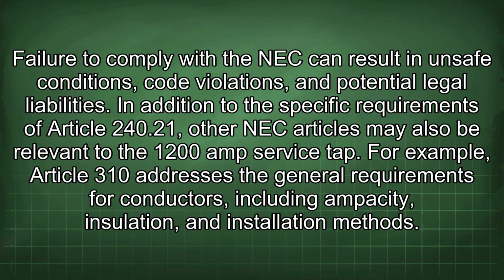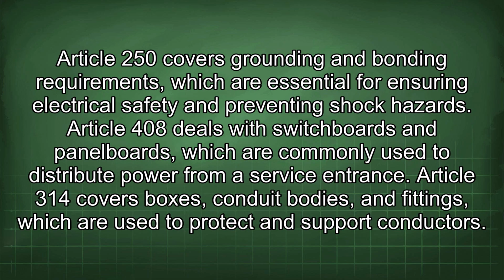In addition to the specific requirements of Article 240.21, other NEC articles may also be relevant to the 1200 amp service tap. For example, Article 310 addresses the general requirements for conductors, including ampacity, insulation, and installation methods. Article 250 covers grounding and bonding requirements, which are essential for ensuring electrical safety and preventing shock hazards. Article 408 deals with switchboards and panel boards, which are commonly used to distribute power from a service entrance.